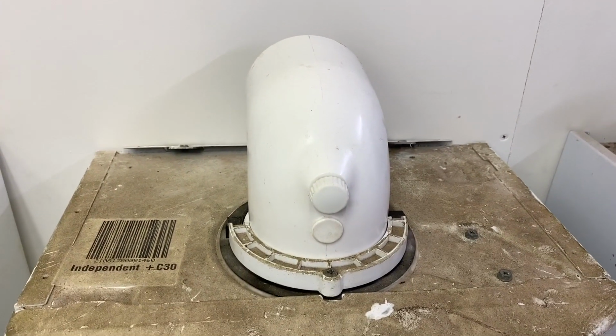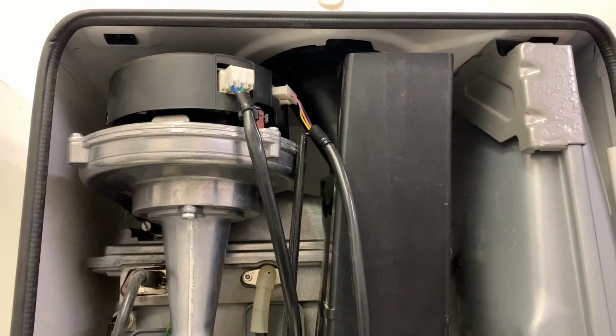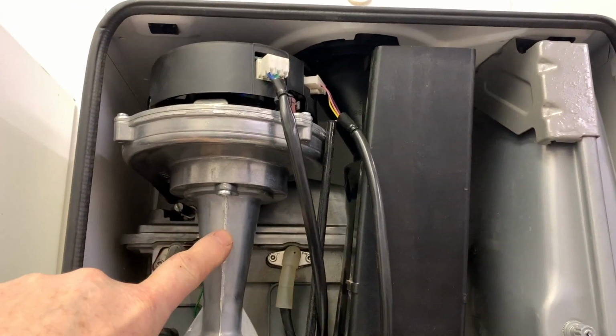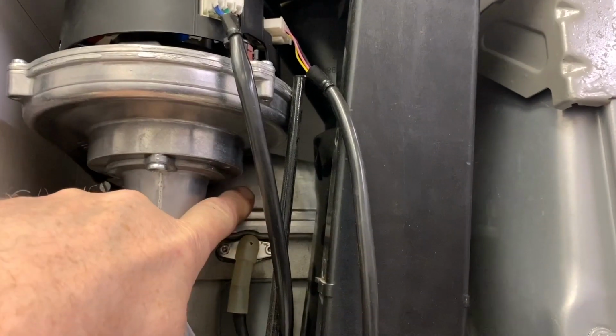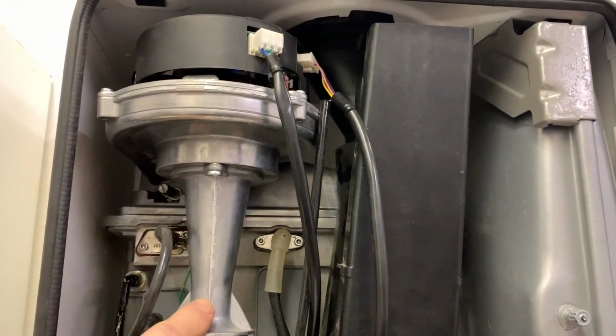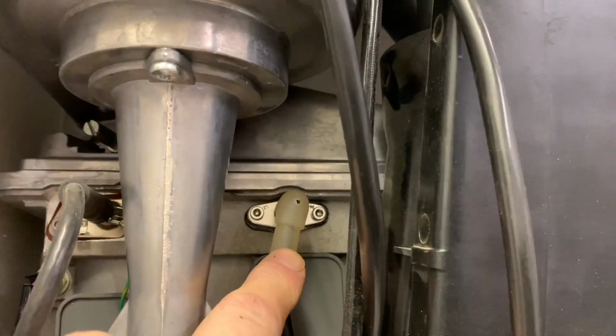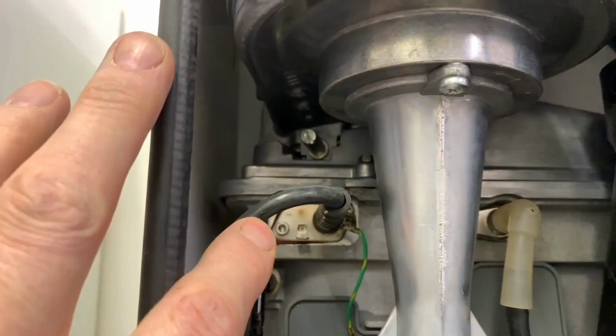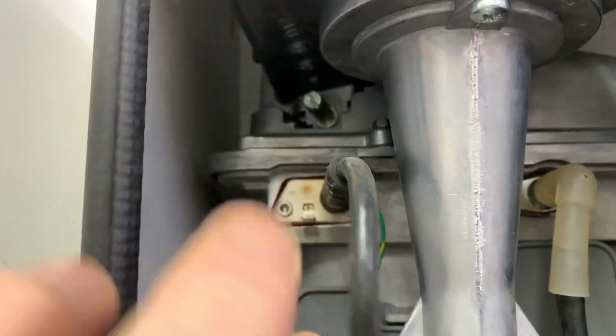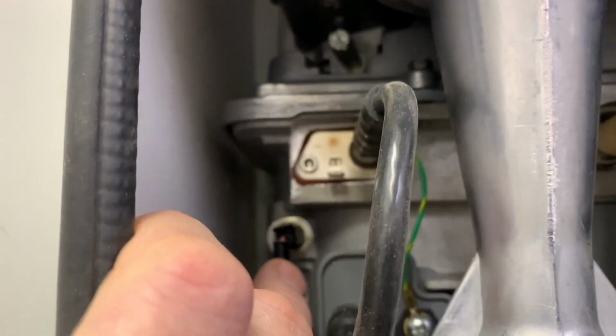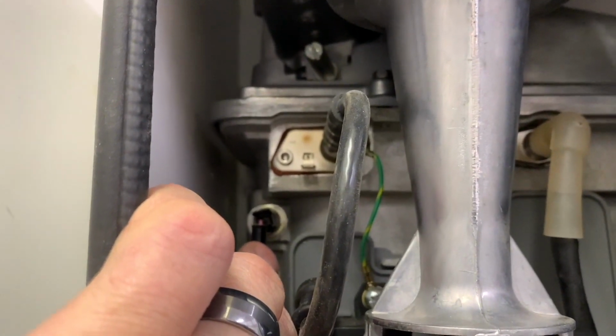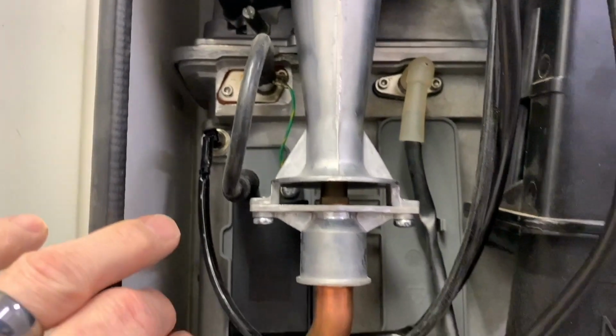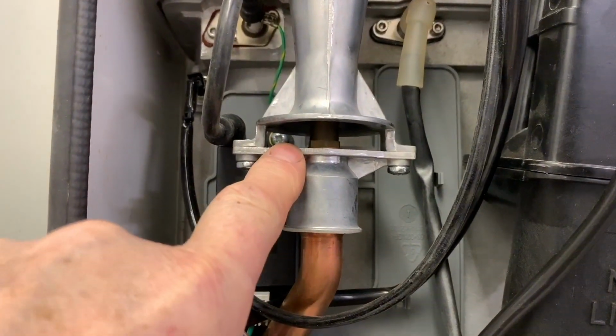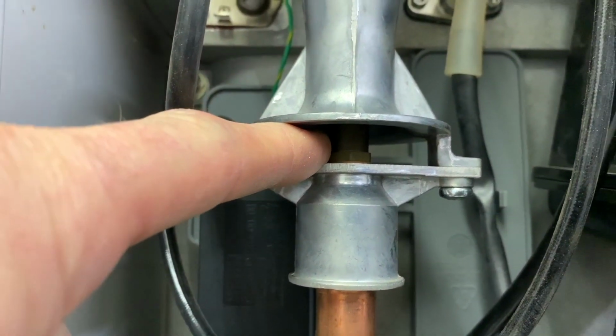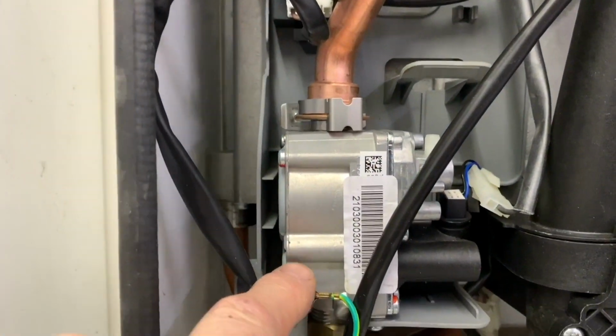So let's get these front covers off and let's have a look at the differences inside. So if we start at the top, what we have here is the fan. Behind the fan you can see the burner. We're going to see all this a lot closer. This here is the flame rectification, and this one is ignition. Now what you've got here, they class this as the hot water sensor, even though it's in the heat exchanger. So that is the hot water sensor. Here is where the air comes in for combustion and it mixes with the gas there. And we come down to the gas valve.